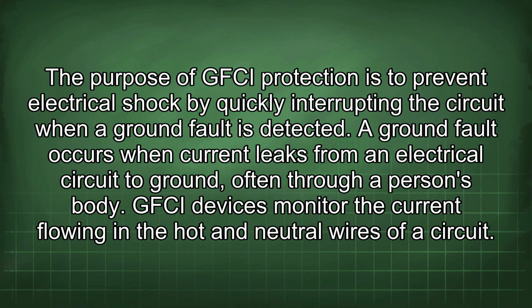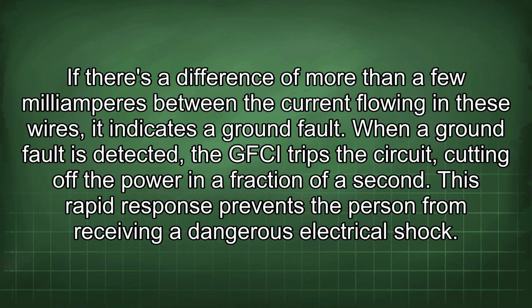The purpose of GFCI protection is to prevent electrical shock by quickly interrupting the circuit when a ground fault is detected. A ground fault occurs when current leaks from an electrical circuit to ground, often through a person's body. GFCI devices monitor the current flowing in the hot and neutral wires of a circuit. If there is a difference of more than a few milliamperes between the current flowing in these wires, it indicates a ground fault. When a ground fault is detected, the GFCI trips the circuit, cutting off the power in a fraction of a second. This rapid response prevents the person from receiving a dangerous electrical shock.